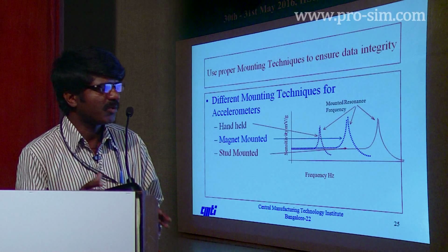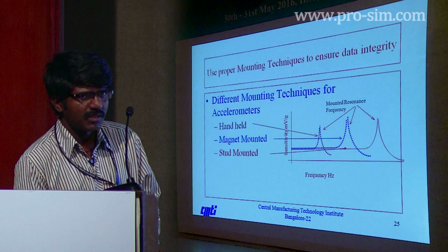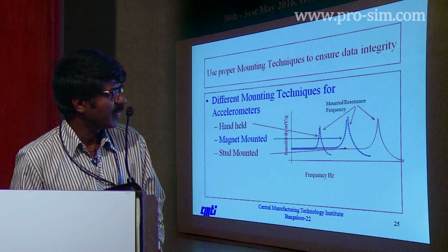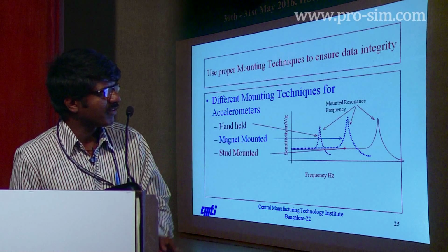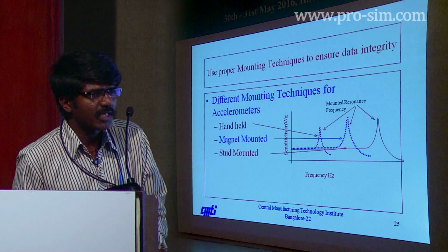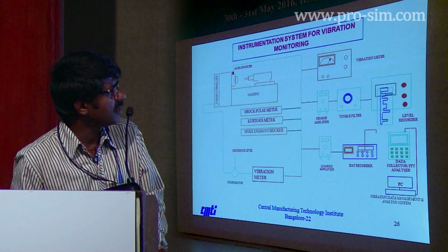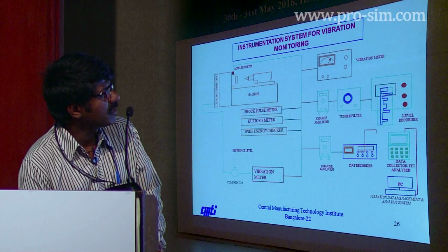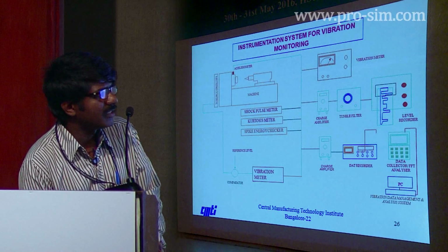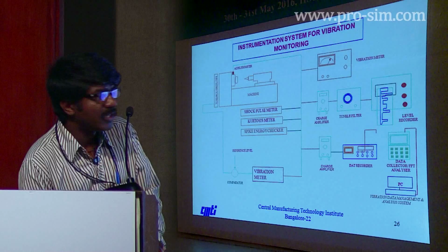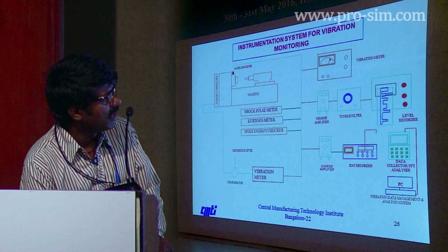We have to use the proper mounting technique. The stud mounted is preferred, so that we can make use of the entire useful frequency range of the accelerometer. This is the typical instrumentation system for vibration monitoring. Here we have taken the example of the lathe. The accelerometer is mounted on the spindle housing.